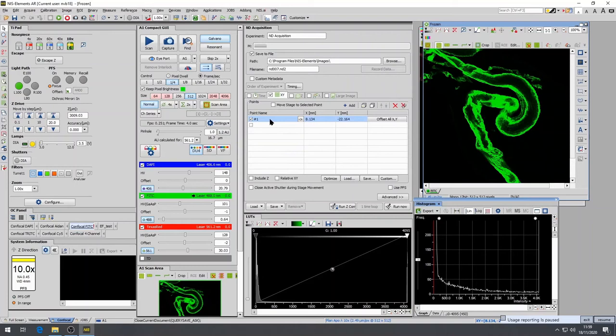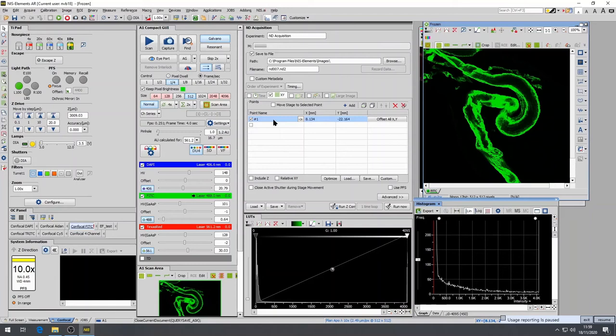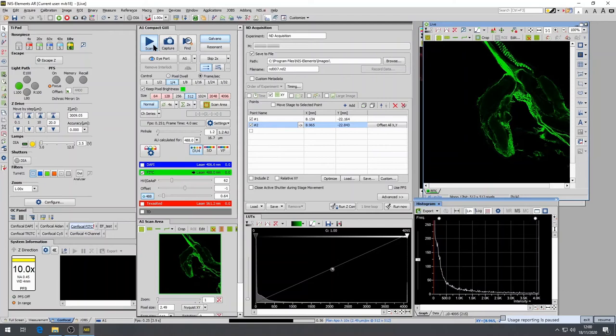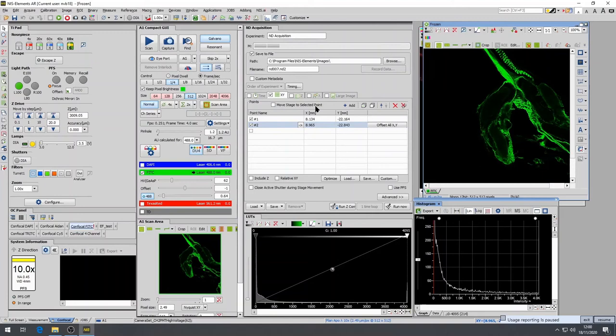If I click in the first row, it will register the X and Y position of the current location, and you can select multiple positions. You can change the point name if you wish. This is particularly useful when imaging in multi-well plates. You can go back to previous locations by pressing Move Stage to Selected Point, which is found just above the point names. And you can update the positional information by selecting an arrow marker that is enabled next to the XY.